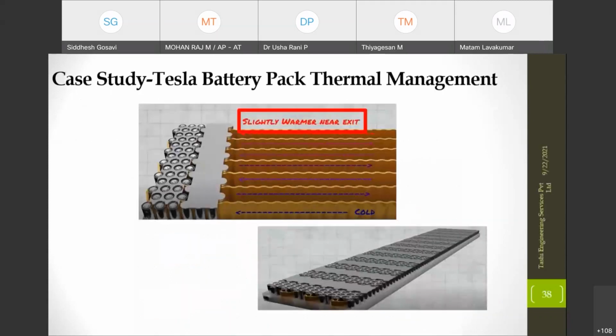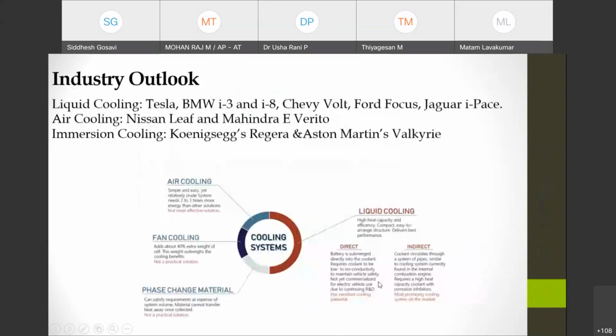Just as an example, if I have to make an air cooling unit for this system, I have to consider inlet ports for the air along the length so that there is no zone in which there are temperature gradients in the air. I also need a very high flow rate of air to have high heat transfer coefficient values. Generally, we cannot have an air cooling unit for such a big battery pack, because then my fan sizing and compressor sizing would be so bulky that it would be beyond the design constraints.